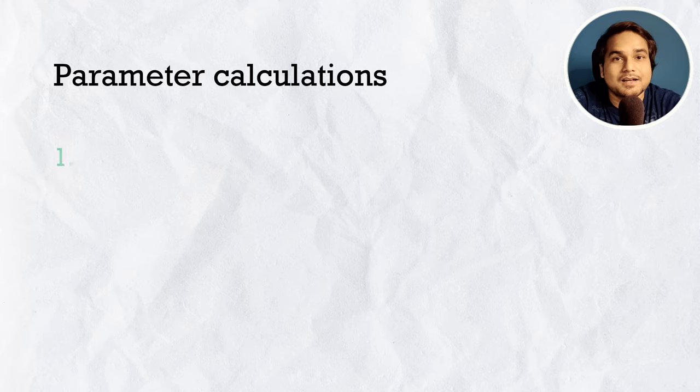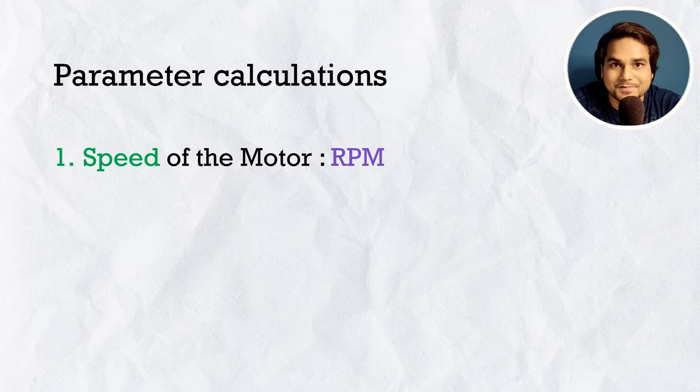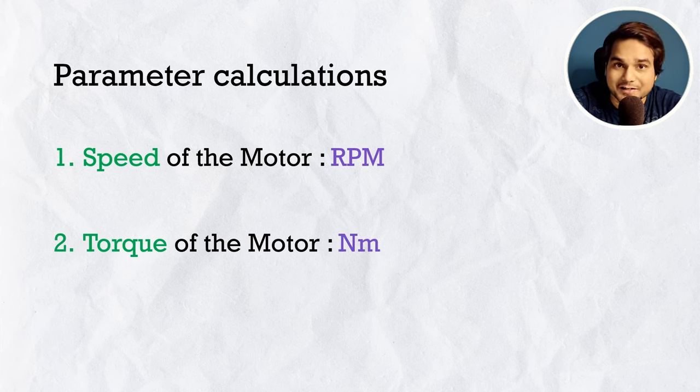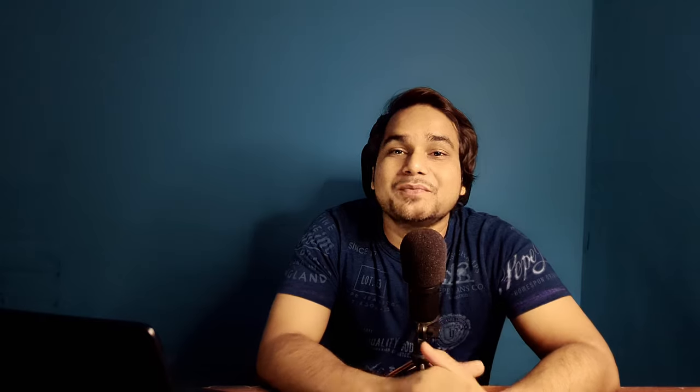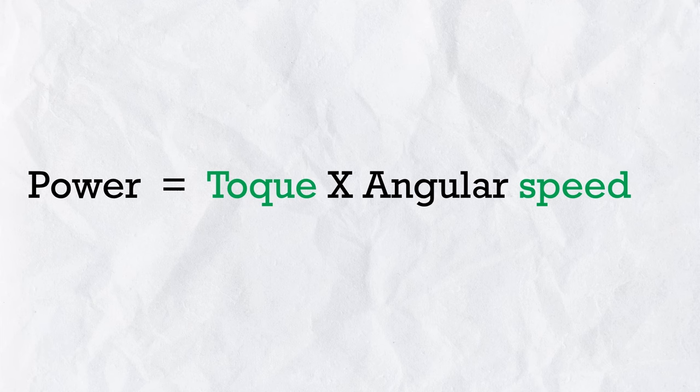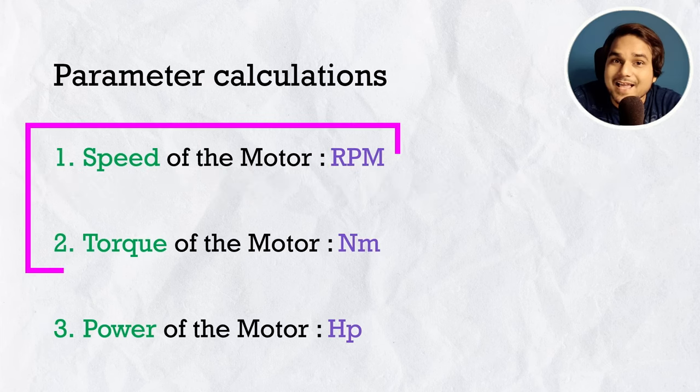First, what are the parameters we need to calculate to make the selection of motor and gearbox for a belt conveyor? Number one: required speed of the motor. Number two: required torque of the motor. Number three: required power of the motor. We only need to calculate two of these parameters because power equals torque multiplied by speed — so knowing any two gives us the third.